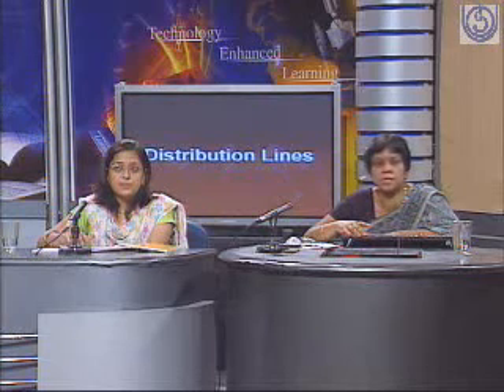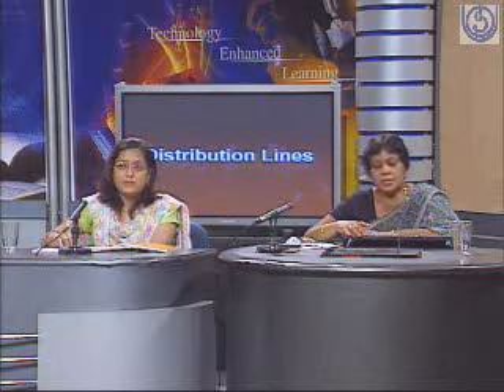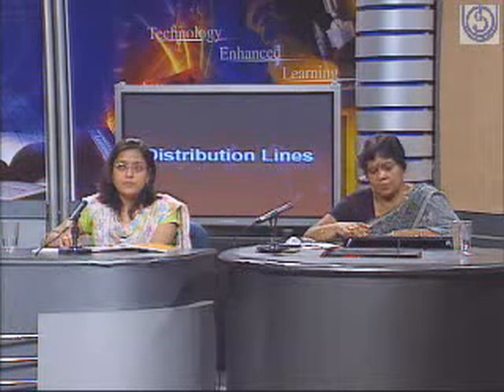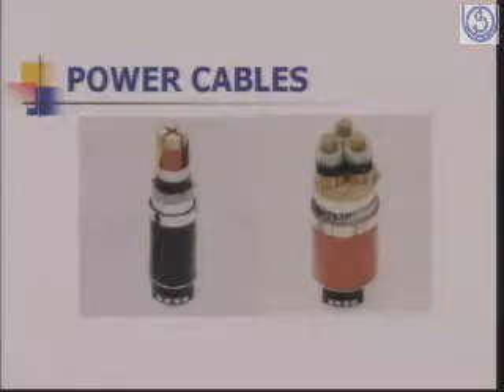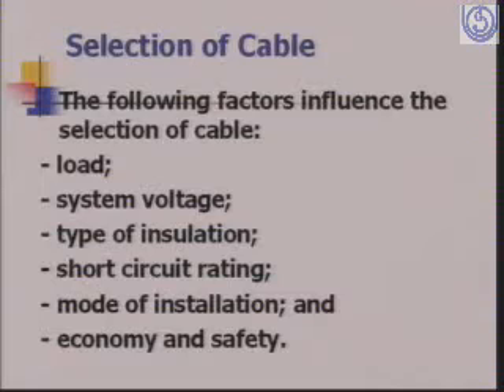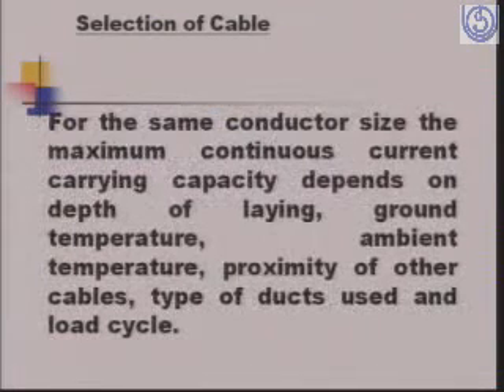So we were talking about underground cables, and a fairly uninterrupted and reliable power supply can be maintained through underground cables. And you can see this is a picture of the underground cables which are being used. They can be of various types, and the factors which influence the selection of the cable are the load, the system voltage, the type of insulation, the short circuit rating, the mode of installation, and economy and safety. For the same conductor size, the maximum continuous current carrying capacity depends on the depth of laying, ground temperature, ambient temperature, and proximity of other cables and types of ducts used and load cycle.